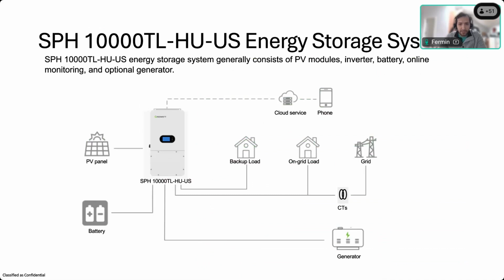So this is a typical configuration. This is what the typical application for the SPH looks like. It comes with integrated CTs, which will go in between the meter and the main service panel. Basically you can connect up to 3 strings on the PV side, DC coupled PV. You'll have the batteries, which I'll go over in a second. And then you would also have the option to connect the generator to the gen ports. You can connect a generator rated up to 10 kilowatts to each inverter. And then yeah, this would be the typical application, although you could use it for small C&I applications or also whole home backup applications.